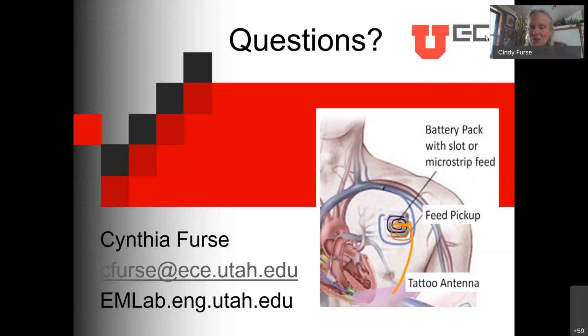So there are two guidelines, and each country uses one or the other: one based on 1 gram SAR, the other based on 10 gram SAR. Although there are also total power limits, they don't end up being the effective limits for implants—it's this localized SAR guideline that ends up being the effective limit. This is already law in virtually all countries, including India, which I believe uses the 10 gram guideline. But yes, it's the SAR guideline that limits the amount of power we can transmit.